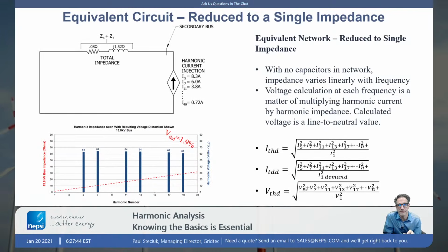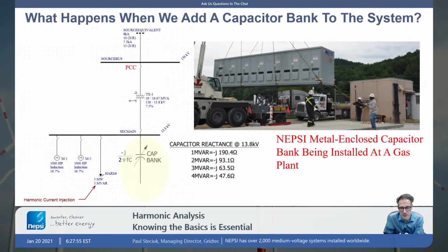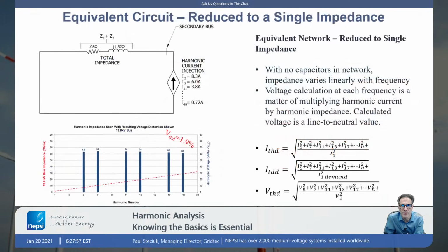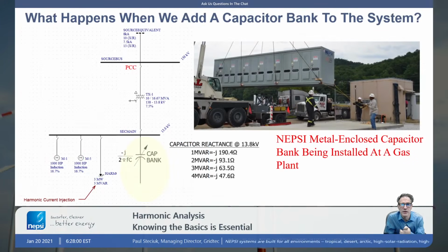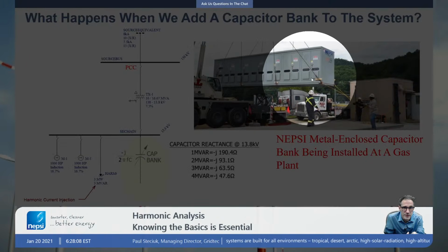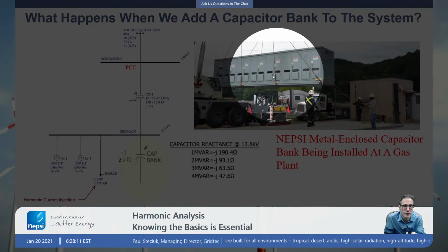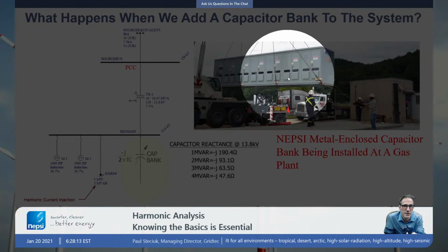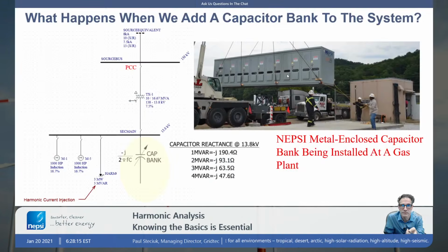So we've already done the most basic harmonic analysis. Very, very simple to do. You're just breaking this problem down into pieces. Let me go back. Okay, I've got it covered. Next slide. Say now you add a capacitor bank to the network, and that's what we're doing here. Here's a typical NEPSI metal-enclosed cap bank being installed within the substation, and you say, well, what can happen? What can happen?